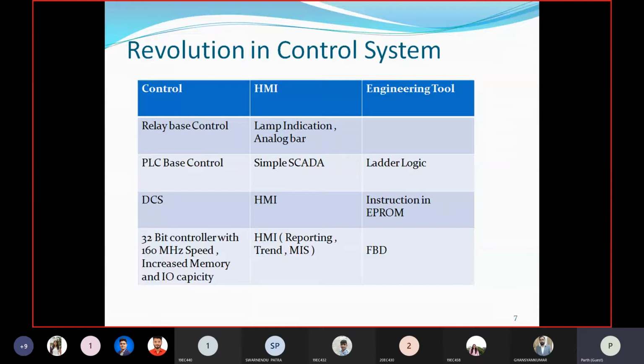Now the advanced controller is a 32-bit controller with 160 megahertz speed, increased memory, and increased IO capacity. We also have HMI available, with advanced features like reporting, trend, and MIS, that is station level server. Then we have function block diagram type logic: there is software in each DCS where one can create the logic just like Paint, and then download that logic into the controller. But you definitely need function code knowledge to create that logic.